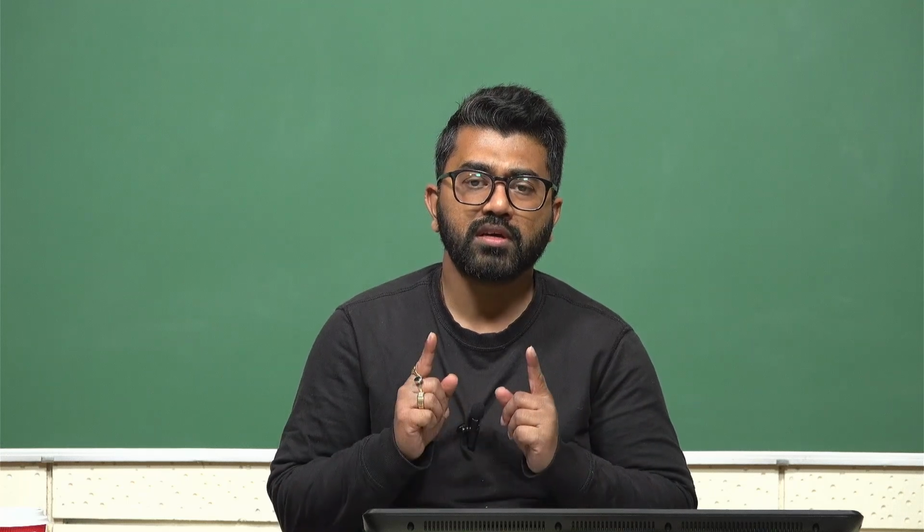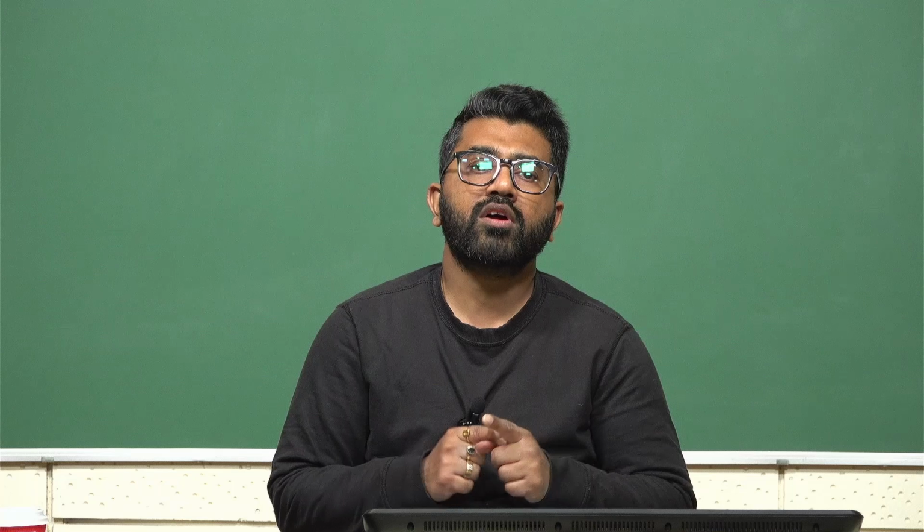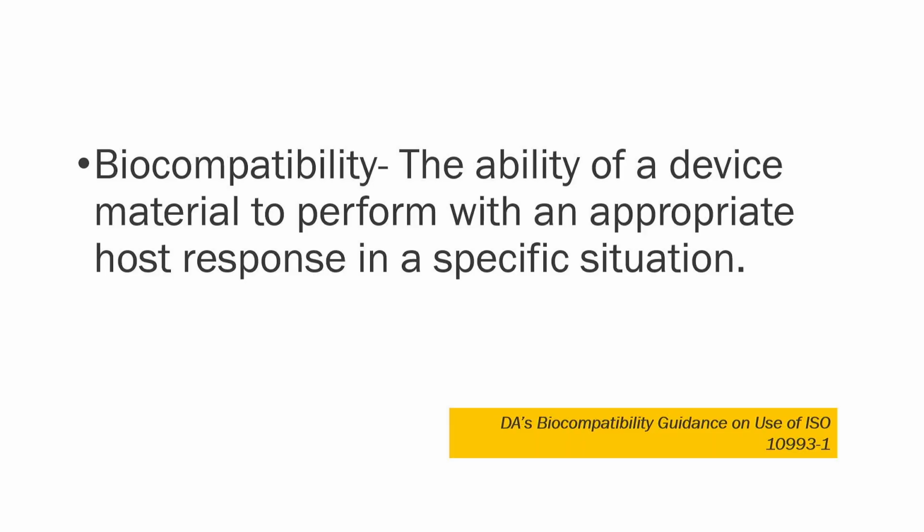So it should not create some inflammatory response, where there's inflammation around the implant or around the tissue. It's not adhering to the natural tissue. Things like that should not happen. So that's the idea of biocompatibility. If we say this particular tissue construct or tissue engineered material is biocompatible, that means it blends in well with the original tissue. Whether it heals or properly integrates mechanically is a very separate problem, but it's compatible. It's not going to generate any adverse reactions. So that is what biocompatibility is as per the FDA's biocompatibility guidance on use of ISO 10993-1. This is based on that handbook.